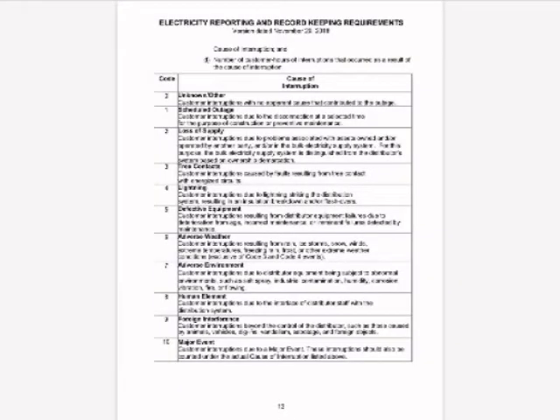So these are all the categorizations that are used when we're looking at causes of outages. And some of these are going to be fault inducing. So typically your fault inducing ones would be trees, lightning, defective equipment, foreign interference, major events. These would all cause a fault. And then scheduled outages, loss of supply, human element usually result in an outage, so no electricity to the customer, but often don't involve an actual failure and a high current, high energy event to occur.